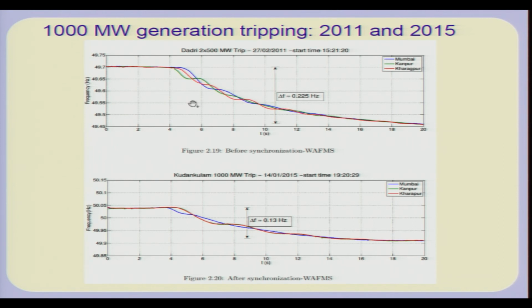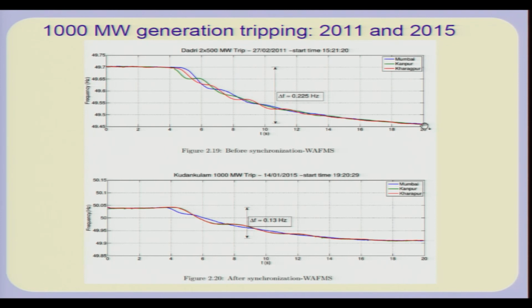The steady state settling frequency for 1000 megawatt tripping in 2011 and 2015 is also different. You will find that the number of loads has increased, and each load has a load frequency dependence. You also have governor action, and because of that, in 2015, for the same 1000 megawatt tripping, there has been a much lower steady state frequency drop than in 2011.